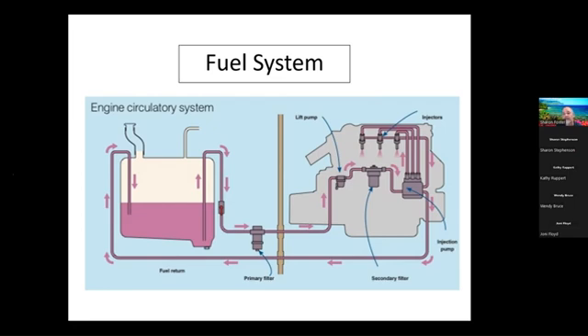From the Racor, the primary filter, it's going to go usually to a fuel lift pump. This can either be mechanical, or in some cases they're electric fuel pumps. From the electric fuel pump, it's going to go to your secondary filter, which is usually provided by the manufacturer and bolted right onto the engine.